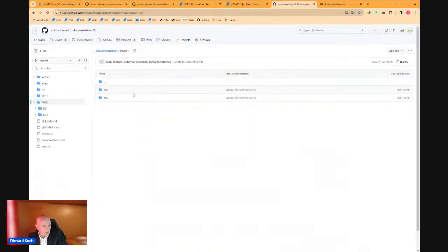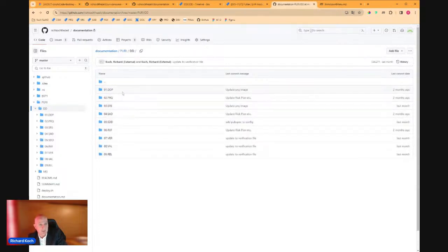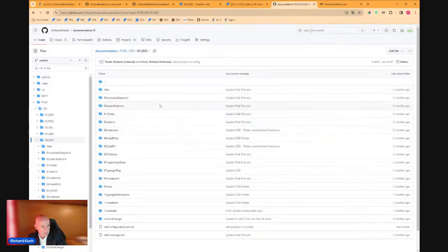And if we work through it, basically I've got two sections here: the development file, that's my design file, and the medical device file. And you see, again, it's pretty simple. I just structure the development file around the stages of 62304: development planning, product requirements, SRS. And I like using just the three-digit codes. Effectively, it just makes things a lot shorter and simpler.